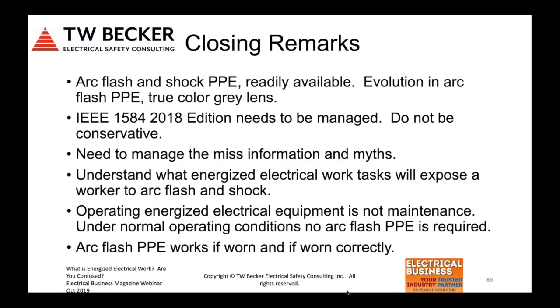So arc flash and shock PPE is readily available. We're having an evolution in that PPE, true color gray lenses for the shields and hoods, the applications of LEDs, and the hood ventilation systems, again, are evolving and readily available. The IEEE 1584 2018 edition needs to be managed. Do not be conservative. Do not panic. Make sure you ask for substantiation from the professional engineer that's going to say he or she needs to redo the entire study, or needs this information, or this is why we're going with this box electrode configuration. And if you're uncertain, ask for a third-party opinion with respect to some of the recommendations being made to you.